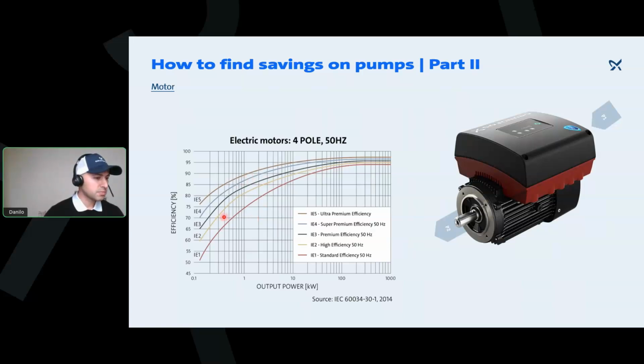You can also notice that the output power will have a very similar curve when you're running them at different speeds. So when you start going at lower speeds, the curve will look very much the same. The difference is that this curve is going to drop down a bit faster, right? So when you have a premium efficiency, high efficiency motor, and you start running it below 800, around 600 RPMs, your efficiency is going to go down really, really fast.